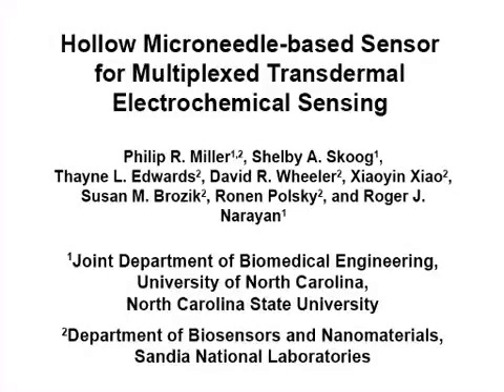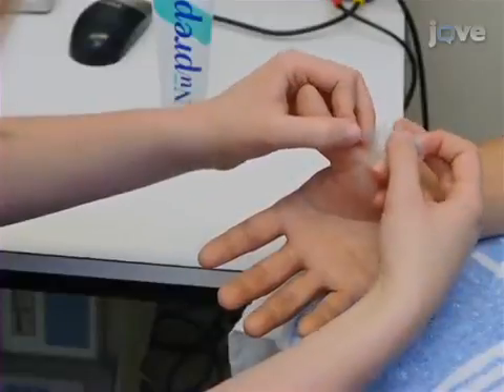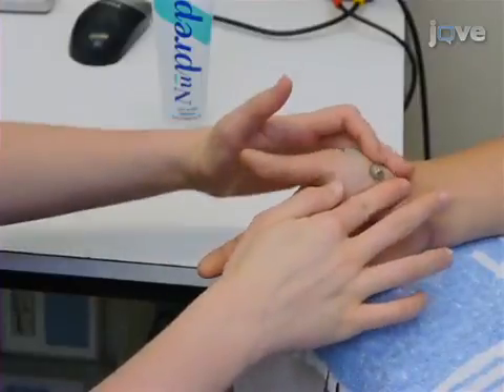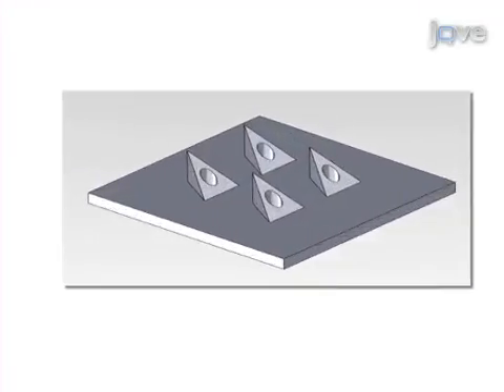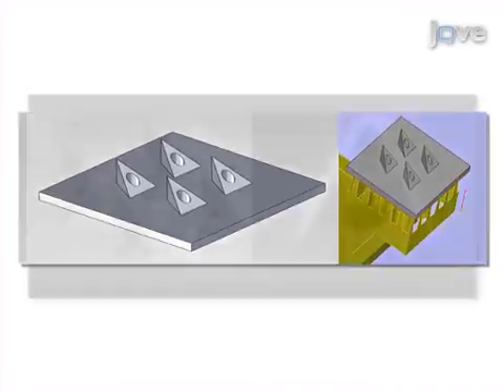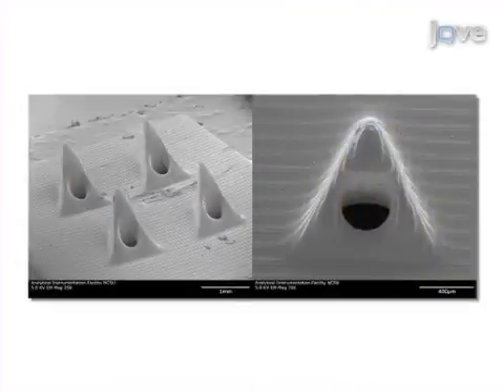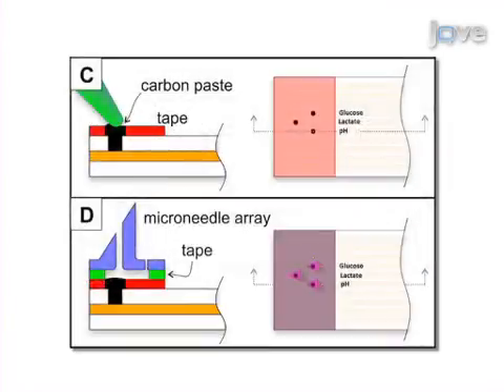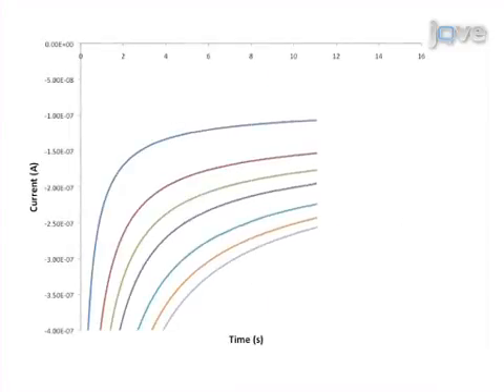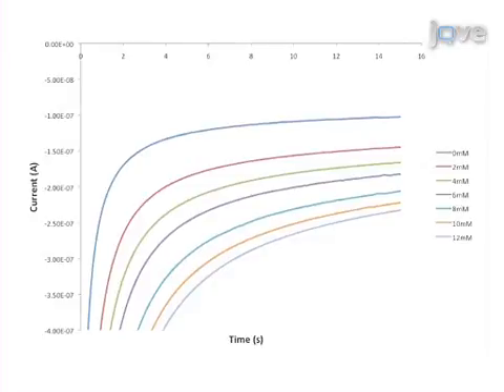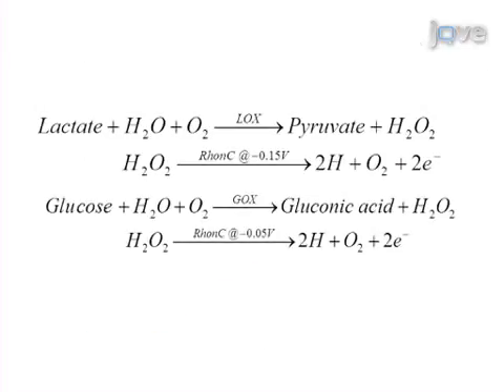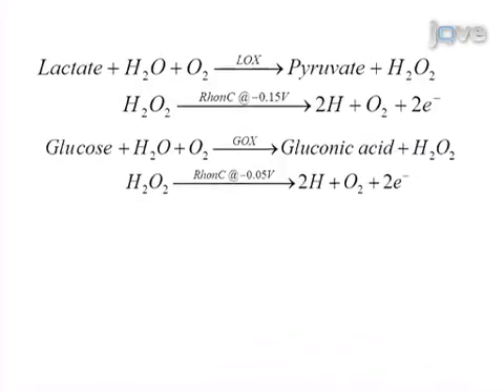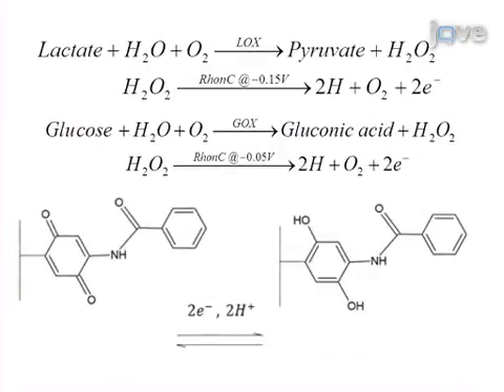The overall goal of this procedure is to fabricate a multiplexed microneedle-based sensor for transdermal electrochemical detection of various target analytes that can be simultaneously measured. The first step is to fabricate hollow microneedle arrays using microstereolithography and create electrode array cavities using laser micromachining. Then prepare the individual carbon pastes and fill the electrode array cavities. Next, calibrate each of the carbon pastes over a range of physiologically relevant concentrations. Ultimately, a transdermal in vivo electrochemical device is created that is capable of simultaneously measuring multiple analytes in complex physiological microenvironments for a range of biomedical applications.